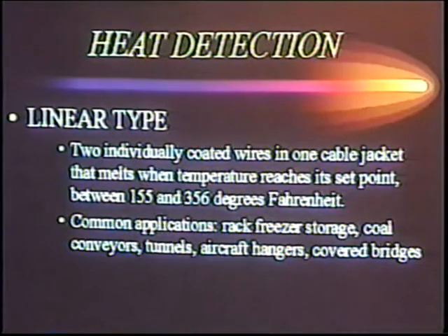Another question: do you use that wire to wire, let's say, a smoke detector? No, you cannot do that. What you can do with ProtectoWire linear heat detection is have, let's say, 156 degree wire from the panel going through a processing facility, with different parts of the facility running at different temperatures. You can mix different temperature ratings on the same wire run. We can't use the wire for a smoke detector, but if you go to a junction box, we can cut the wire and come back in.